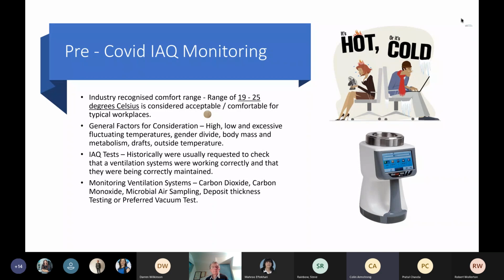I have a personal preference for the deposit thickness testing, because for me it's very black and white. You just put it on the ductwork and it will tell you how thick the dust is. With the preferred vacuum system, I have a slight concern that an engineer might go along to site and put the tube on the ductwork, and he's not going to give it a very vigorous hoover. Let's say he's been doing it all day for 8 hours, and he's going to think, oh, I've got to get home for my tea at 5, so I'm going to spend 5 minutes doing this. So he'll give it a little scrape over. He might hold the tube at a different angle and not have it flat on the dirt to pick it all up. So for me, I just prefer the deposit thickness testing. The preferred vacuum test is recognised, but for me it's a little bit flawed, I must admit.